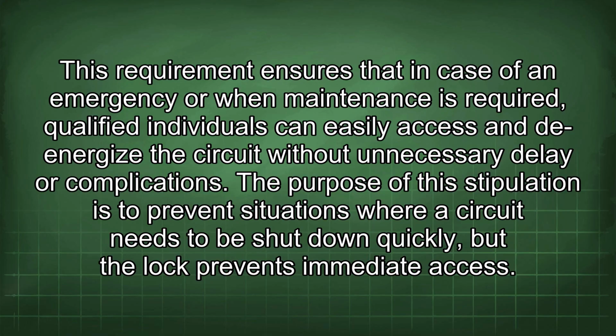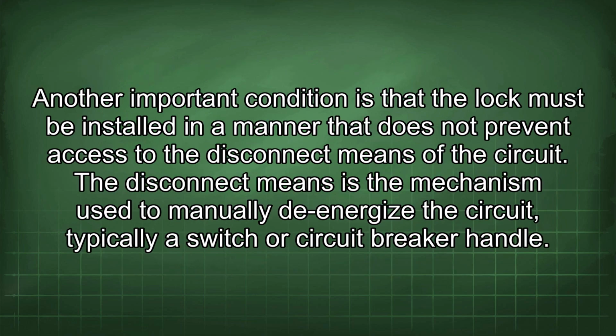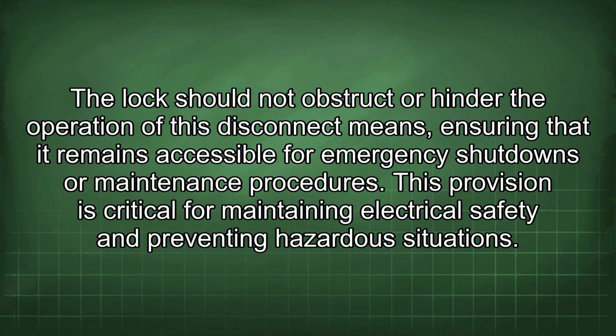The purpose of this stipulation is to prevent situations where a circuit needs to be shut down quickly, but the lock prevents immediate access. Another important condition is that the lock must be installed in a manner that does not prevent access to the disconnect means of the circuit. The disconnect means is the mechanism used to manually de-energize the circuit, typically a switch or circuit breaker handle. The lock should not obstruct or hinder the operation of this disconnect means, ensuring that it remains accessible for emergency shutdowns or maintenance procedures. This provision is critical for maintaining electrical safety and preventing hazardous situations.